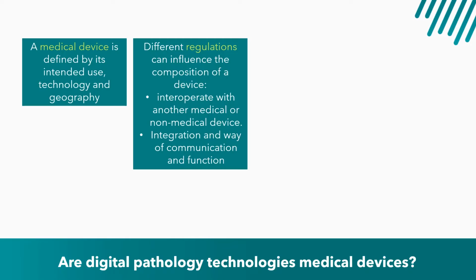For example, interoperating devices in Europe could be considered separate medical devices that exchange information with each other, or subsystems that can be regarded as a closed system, for example, one device. In the USA, the FDA guidance, the Technical Performance Assessment, describes a whole slide imaging system as two subsystems. One is the image acquisition and two is the image display. This is not new to most of us, yet it's relevant to realize this once more. Why? Well, because this approach of this imaging chain is also being followed for algorithms. One can understand when the input differs, for example, the resolution or the compression level, that the algorithm could provide different outputs. This is asking for interoperability.